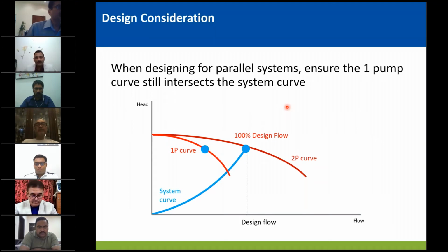So when designing for parallel systems, let's look at this two pump system curve. You have the thick red curve, which is a two pump curve, and that's the 100% design flow. It's common knowledge that when pumps are selected in parallel, it has to cut the first pump curve so that it falls into the system curve. So the blue line is the system curve, or the system natural resistance, balanced resistance. Now, when the first pump fails, the second pump should still work and deliver required flow in the system.